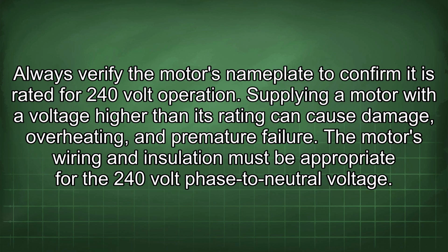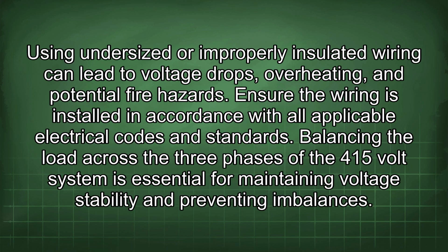The motor's wiring and insulation must be appropriate for the 240-volt phase-to-neutral voltage. Using undersized or improperly insulated wiring can lead to voltage drops, overheating, and potential fire hazards. Ensure the wiring is installed in accordance with all applicable electrical codes and standards.